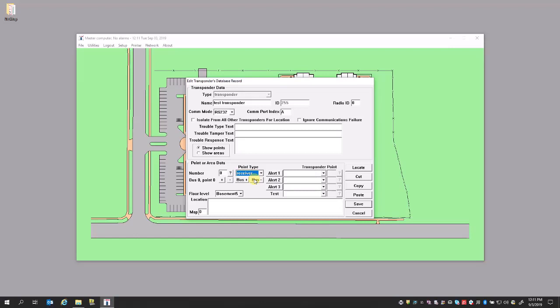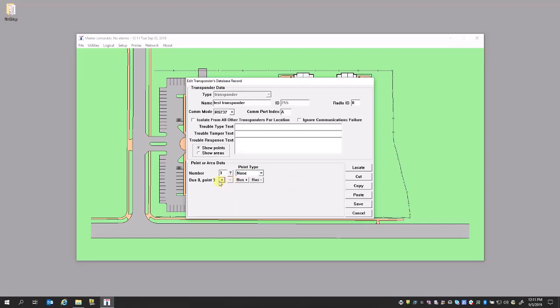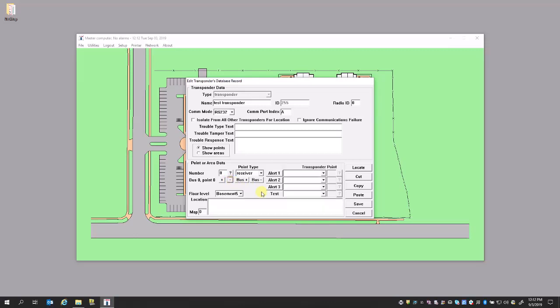We're going to select Receiver. As you can see, we have Bus 0.0. This bus number is 0 through 7 because there are 8 buses on the transponder, and 0.0 is out of 0 through 7 because it can have up to 8 receivers per bus. You can adjust this number using the plus and minus buttons, and it will shuffle through all the buses and all the points. The floor level is whatever floor level the receiver is going to be on — for this, we're going to use Floor 1.